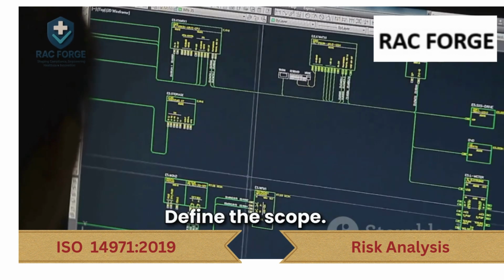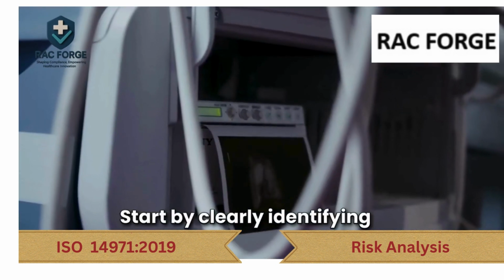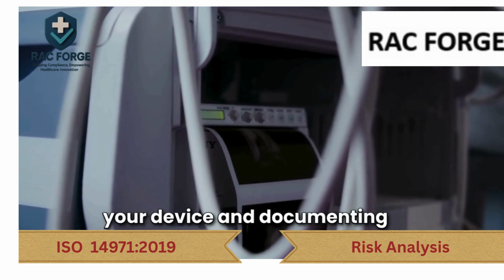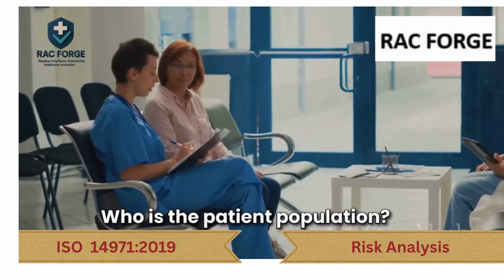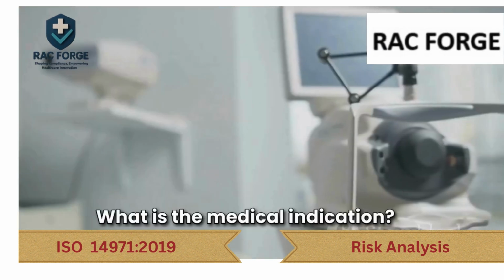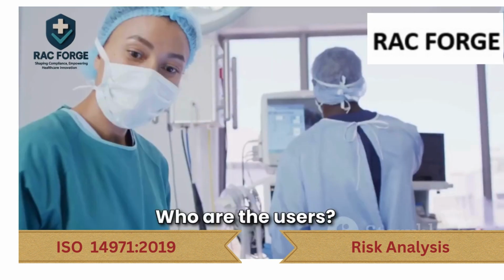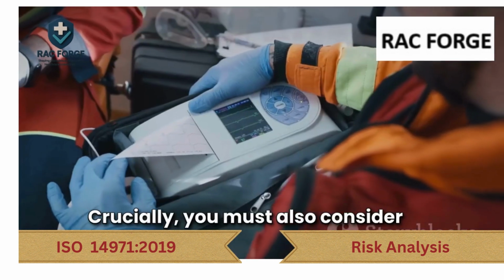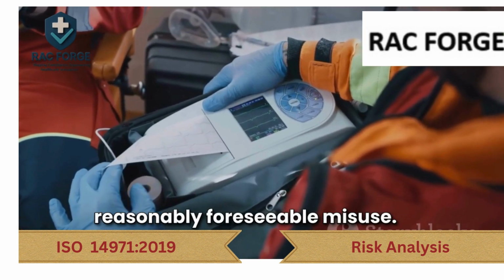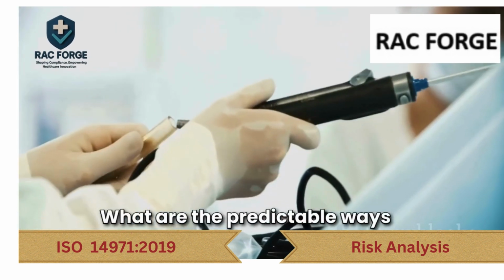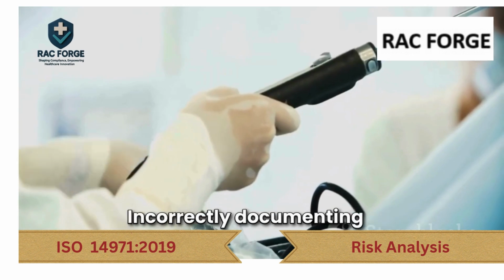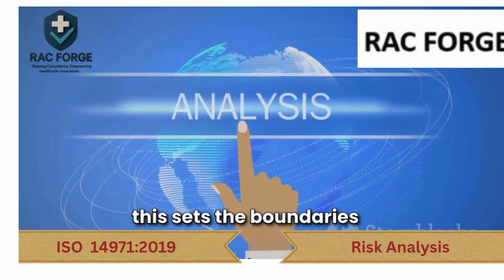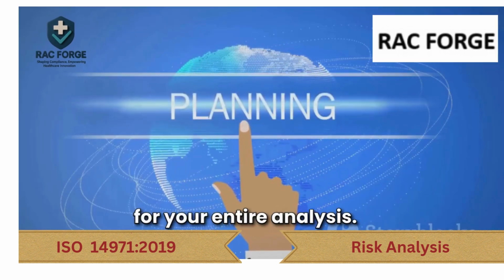Now for step 1, define the scope. Start by clearly identifying your device and documenting its intended use. Who is the patient population? What is the medical indication? Who are the users? Crucially, you must also consider reasonably foreseeable misuse. What are the predictable ways someone might use the device incorrectly? Documenting this sets the boundaries for your entire analysis.